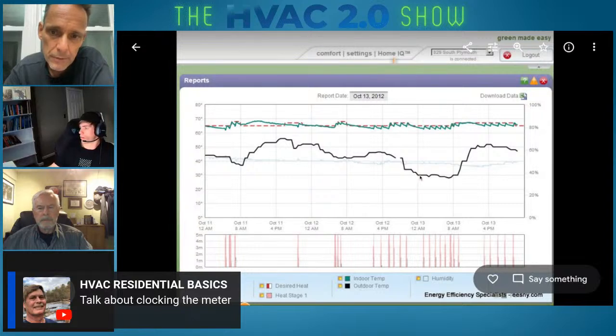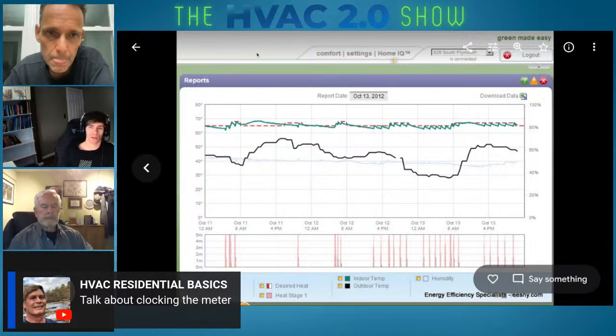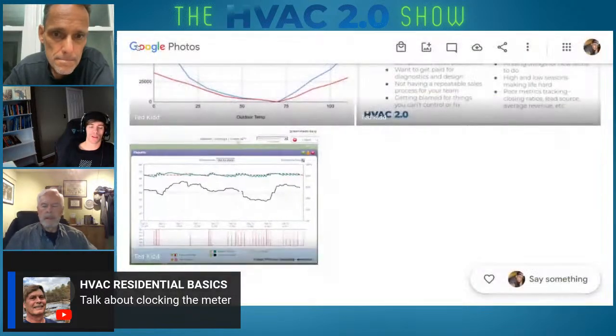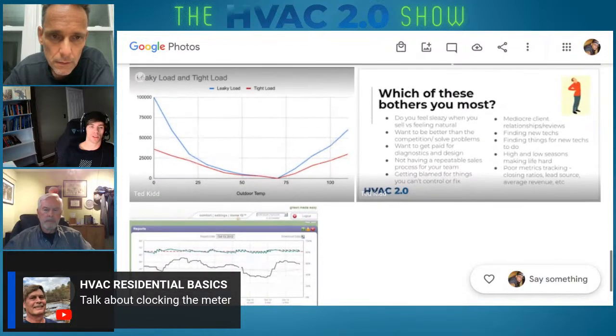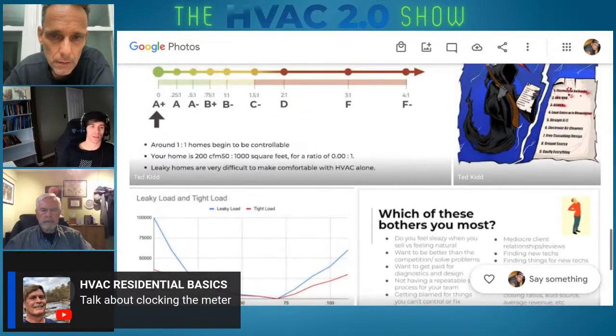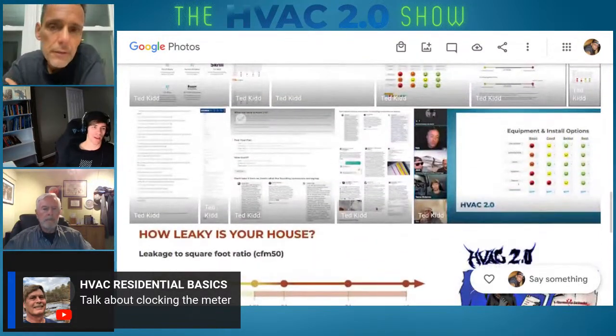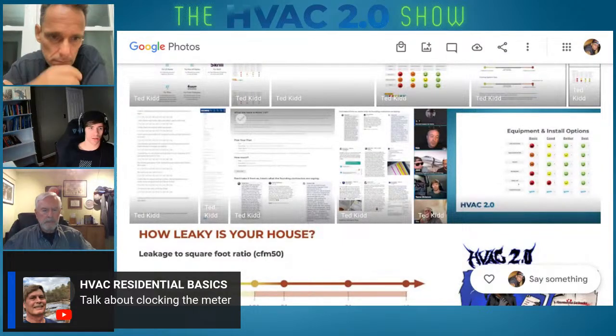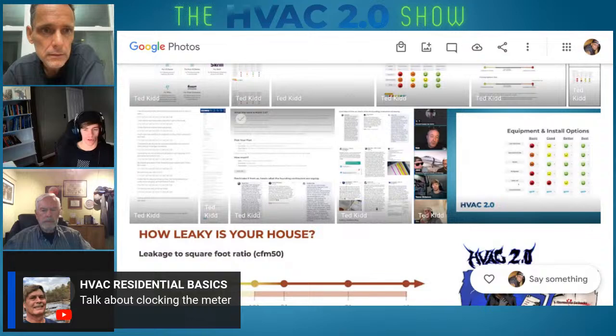Because then you're able to look at outdoor temperature, indoor temperature, and run cycle. I'm not sure what the conversation was before I got here, but he could be talking about setting the gas input to the furnace, just having the gas furnace set up properly. So, like if it's an 80,000 BTU furnace, making sure you're getting 80,000 BTUs of gas to it, to set the gas pressure and such.